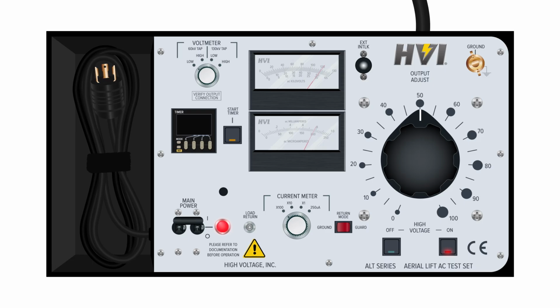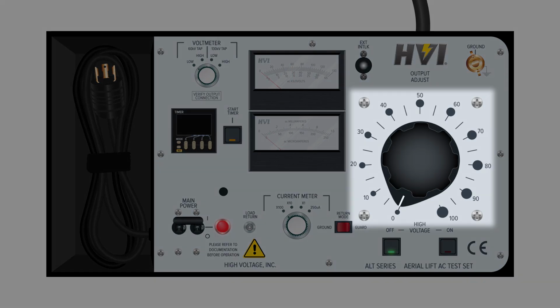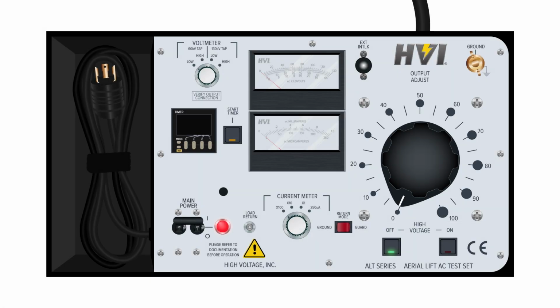When the device is set to guard position, the current going to ground is shunted around the current meter, and only the current through the load return lead is displayed. ALT series Hipots have an output dial located on the right side of the control panel. When safety conditions are met and the high voltage circuit is energized, the output dial will control the amount of voltage being applied to the DUT.